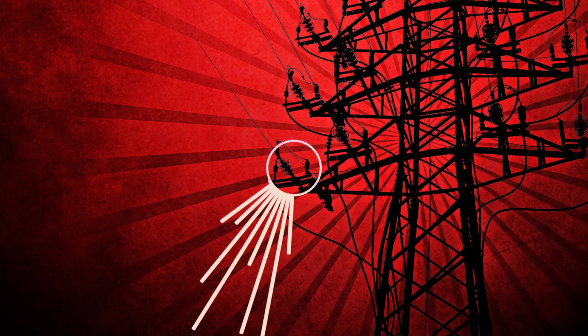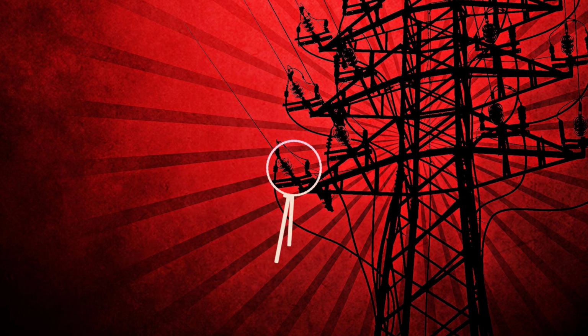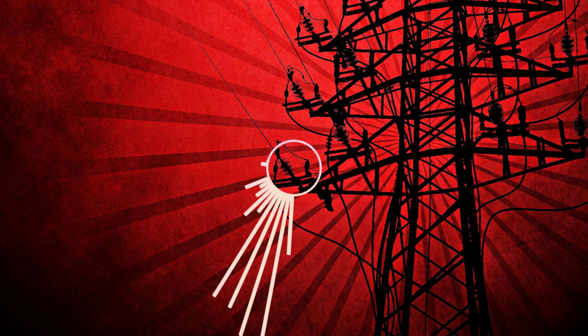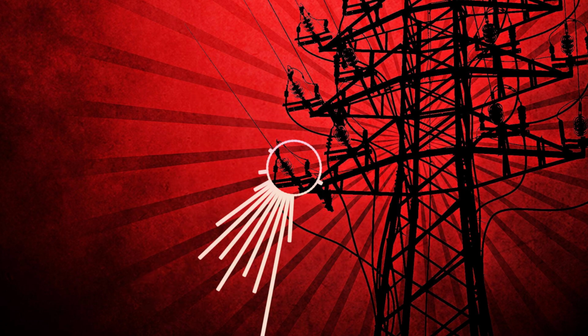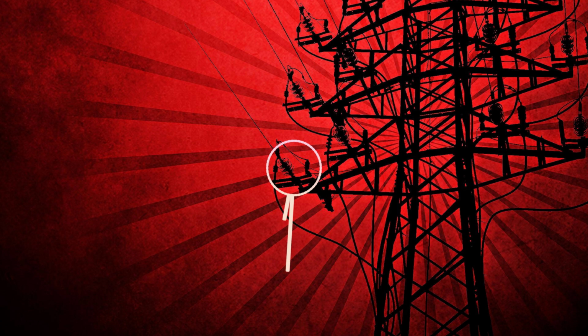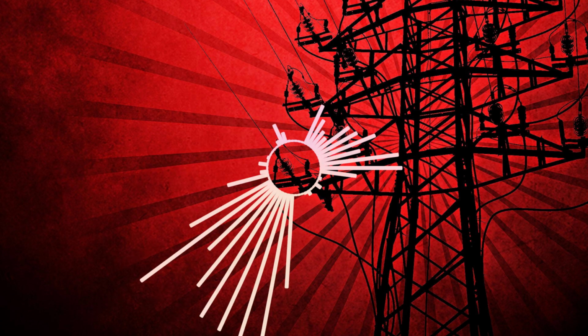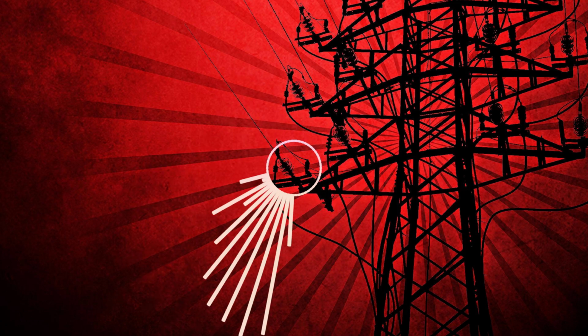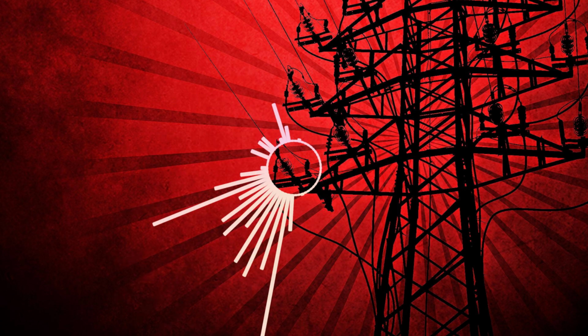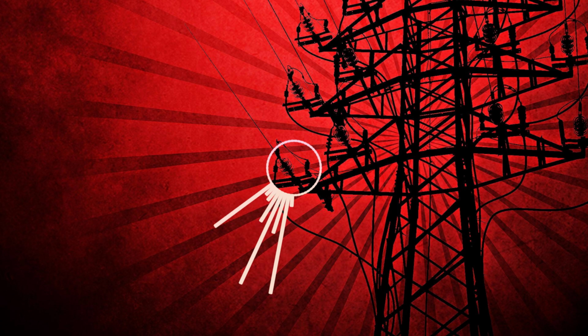This rule tells us how deep the space in front of the electrical gear needs to be. That depth means how far you can stand back from the face of the equipment when you're in front of it. And it's not just a random number. It depends on the voltage of the equipment and the type of surface directly across from it. To figure out how much working space you need, the NEC uses something called working space conditions. There are three conditions listed in Table 110.26(A)(1). Let's break them down.